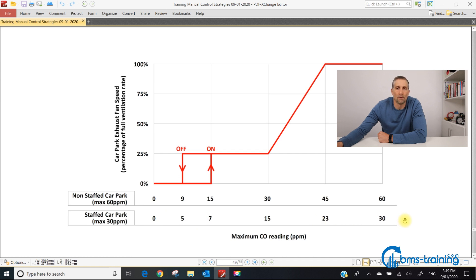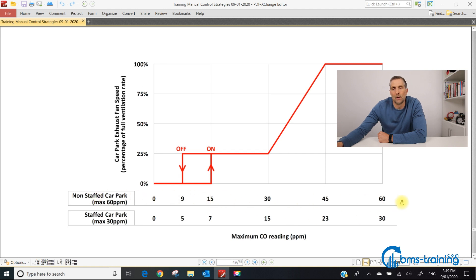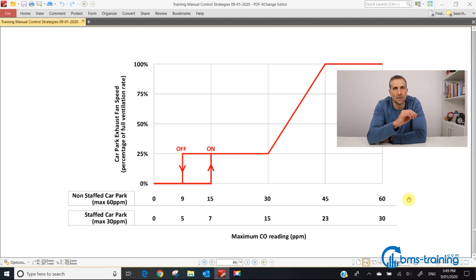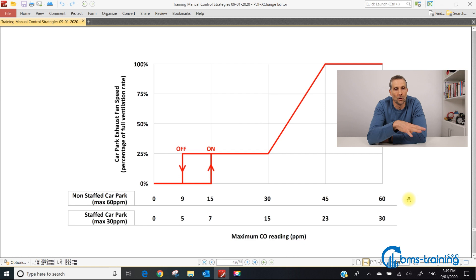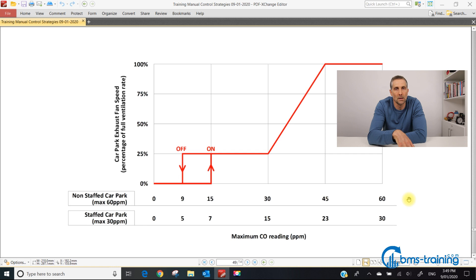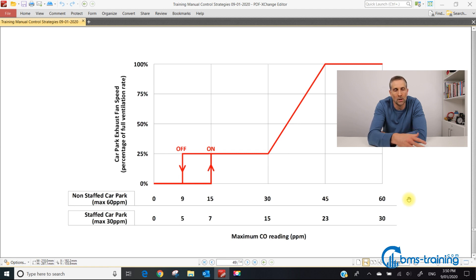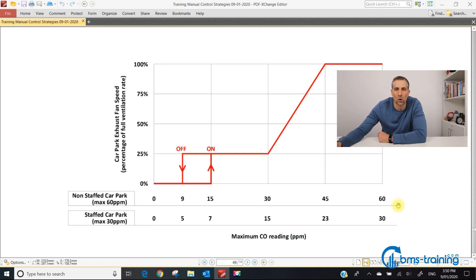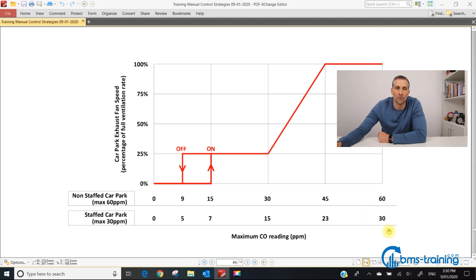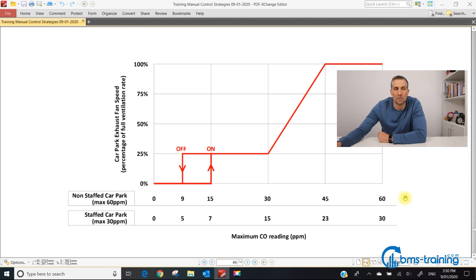Most commercial offices are non-staffed car parks using these values up to 60 parts per million. This is a question worth asking. If you're doing a BMS upgrade, ask the facility manager if it's staffed or non-staffed. In new construction, send an RFI because the values are dramatically different. Programming at 30 ppm for staffed will use much more power than 60 ppm for non-staffed.